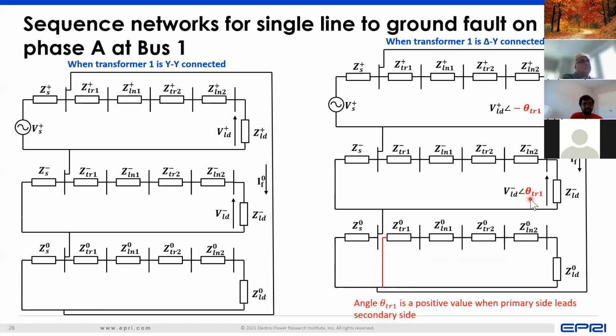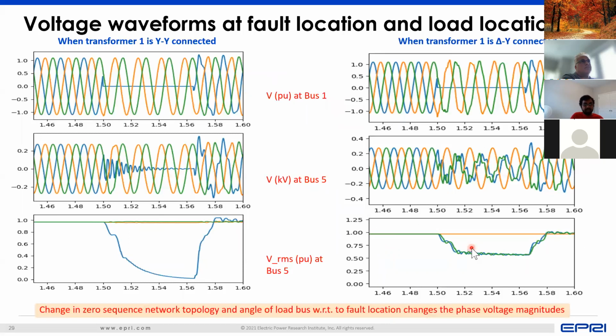What that will result in is it will change the way in which the load, that is the DER in this case also, will see that single phase fault, and it will differ between whether the transformer is star-star connected or delta-star connected. And what really happens is if the transformer is star-star connected, you will have a lower voltage at the load end.